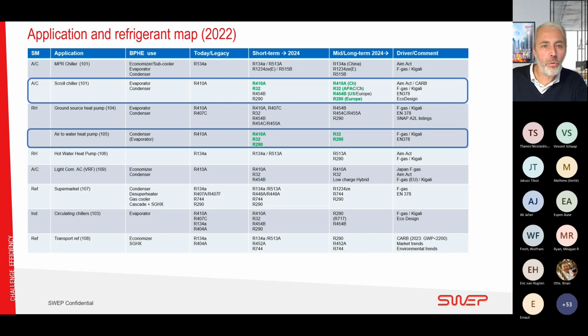Moving on to the application and refrigerant map, I have listed a number of different applications where BPHEs are widely used. In the first column, we have air conditioning, residential heating, and refrigeration. Those are our own definitions. We have the application, how the BPHE is used, what refrigerant is used today, typically the legacy refrigerant, what we believe will happen short term until 2024, and then what will happen mid to long term from 2024, and some drivers in the last column. Since it's quite a busy slide, I will focus on two applications here, the scroll chiller and the air-to-water heat pumps.